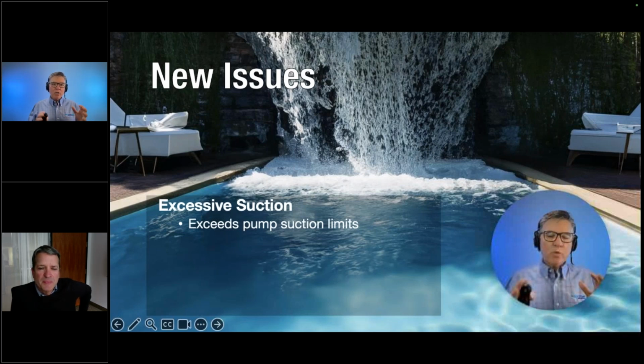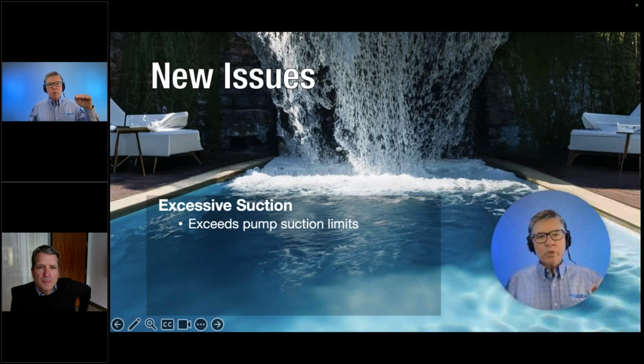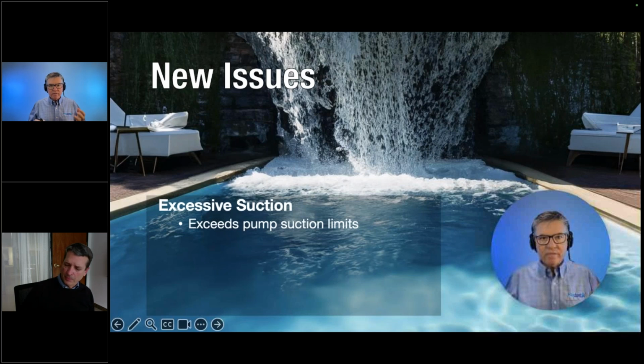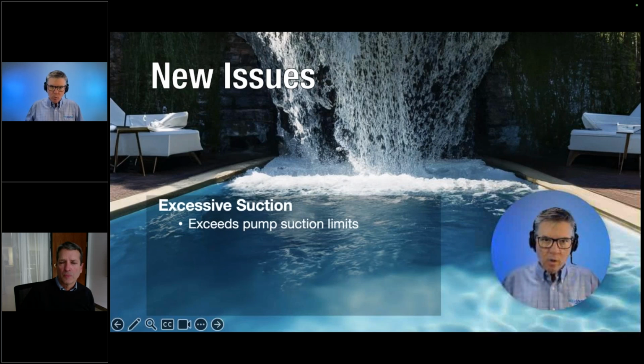Okay, so swimming pools and swimming pool pumps are really 2 pump systems. Gravity pushes water through the pipe to the pump. The pump pushes water out of the impeller diffuser back to the pool. So it's important to understand that water, the physics of water, is it is a particle. To understand what moves water, think in terms of sand. You can't grab a handful of sand or a handful of water and walk away from the bucket or the pool like it's a rope. Okay, you can't pull water, right? The only way you can move water is to push it.